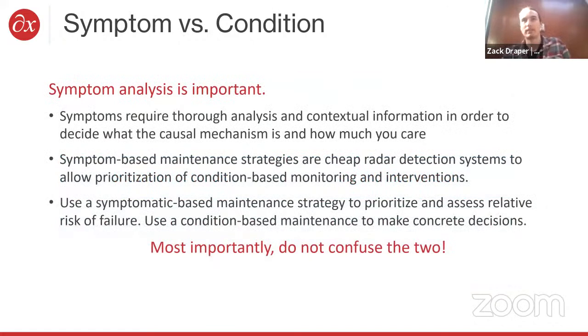Symptom analysis is important because of its utility, low cost, and non-invasiveness, and it allows prioritization of condition-based maintenance. It's basically your high-level radar system to make you aware of your fleet as a whole. You use symptomatic-based maintenance to prioritize based on risk, and then condition-based maintenance tells you more concretely whether or not the transformer is serviceable.